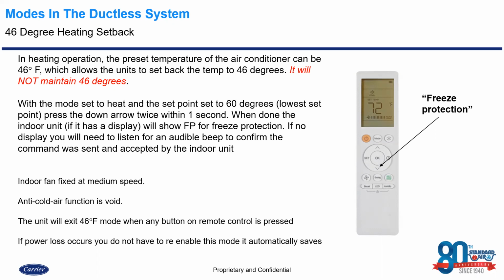Okay, if you don't hear an audible beep, obviously the command wasn't accepted and it's not going to go into the setback function. In this setback function, that indoor fan is fixed at a medium speed. The anti-cold air function is void, which means it's not going to wait for that coil to warm up when it needs heat. If it goes below 46, it's just going to kick the fan on. The unit will exit this setback mode when any button on the remote control is pressed. So it's important to know that the customers don't accidentally press buttons after setting it in this specific feature. Otherwise, it will take it out.